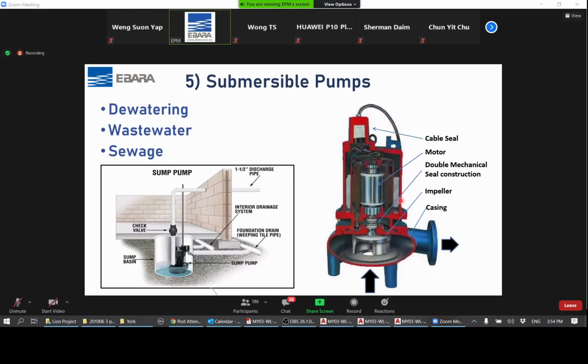Between the wet part and the dry part of the motor there would be an oil chamber, and usually an oil chamber here will have two seals. The bottom seal is usually called a lip seal, which is a simpler seal, and the top part that separates this oil chamber from the motor compartment would be a mechanical seal. There's always an oil chamber here because if there's any leakage of the wastewater inside the pump, the oil chamber would block the water from going into the motor area. Of course you don't want water to get into the motor area, so there's double protection here from an oil chamber.